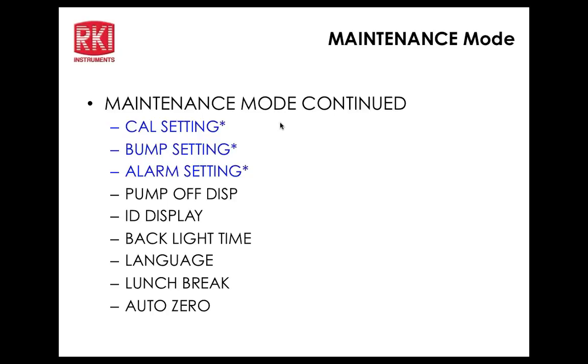And on the calibration? Let's take a look. It's going the other way, about 90 total, 60 for the application of the gas, because remember we're in the bump function right now. So it looks like 90 is the lowest. You'd have to check the total. I think if you go to the cal time you can change it. Right, in the cal setting, exactly. Let me lock that in.